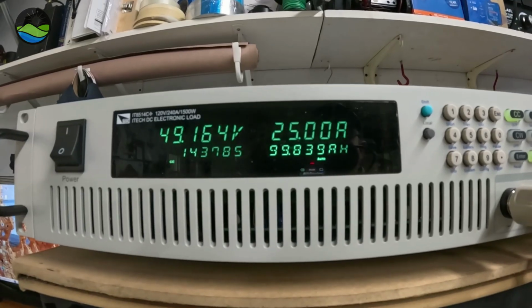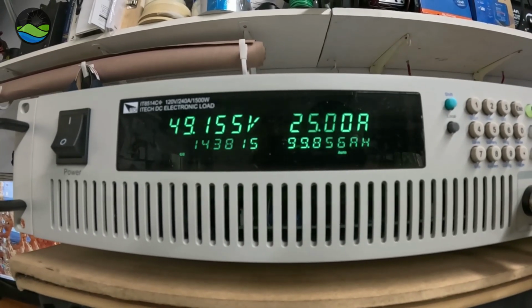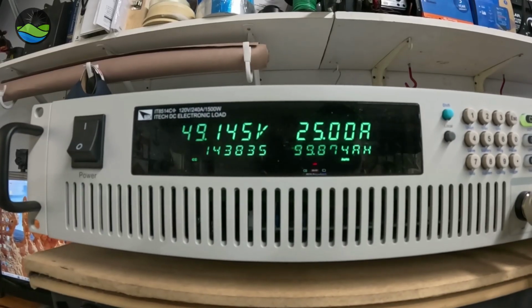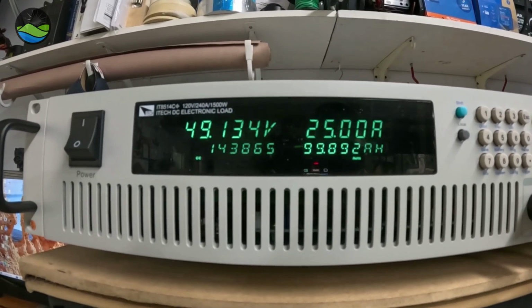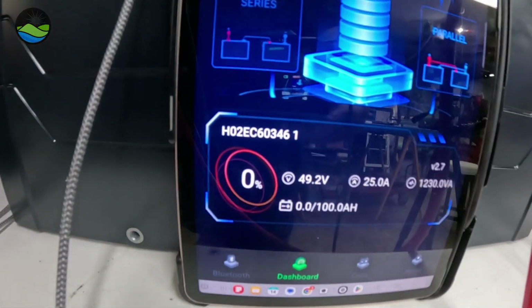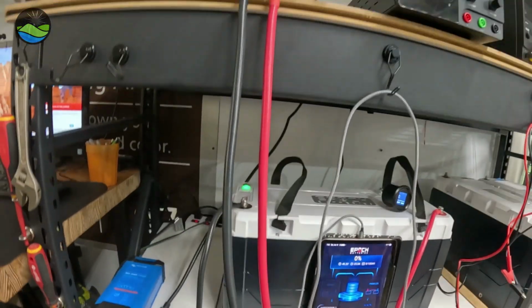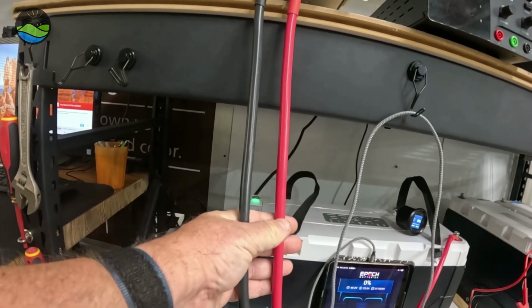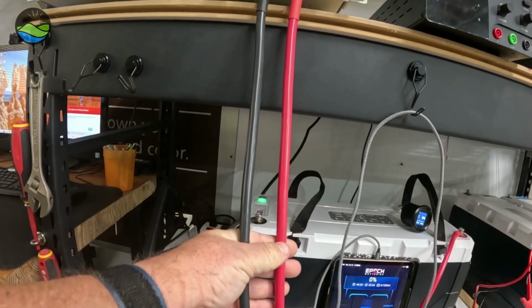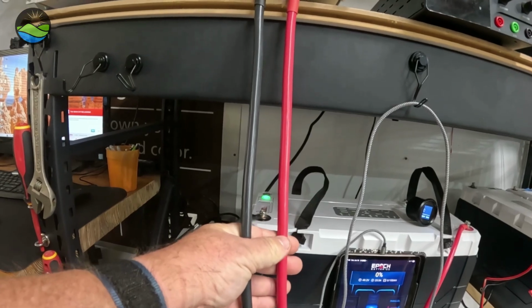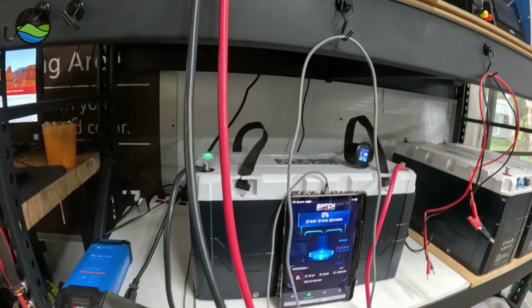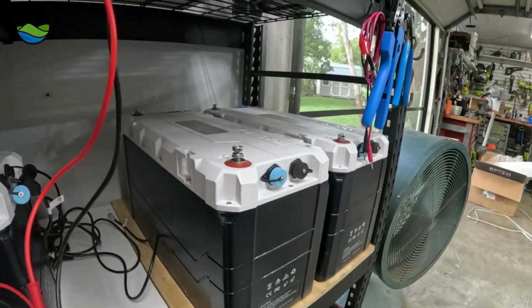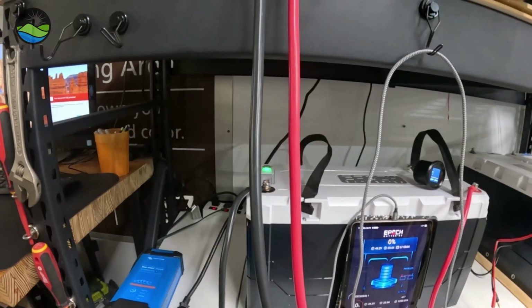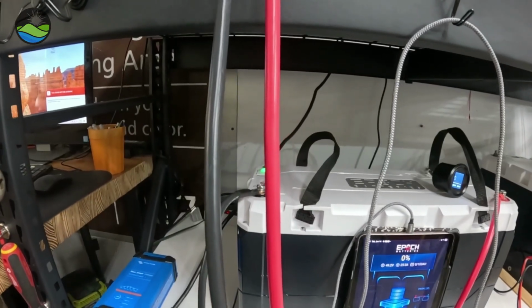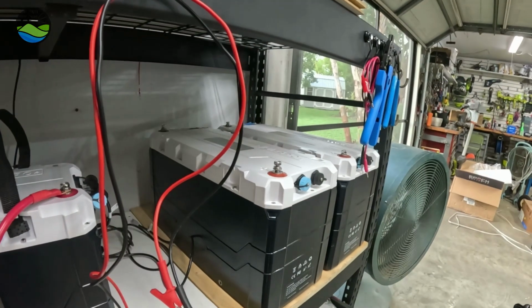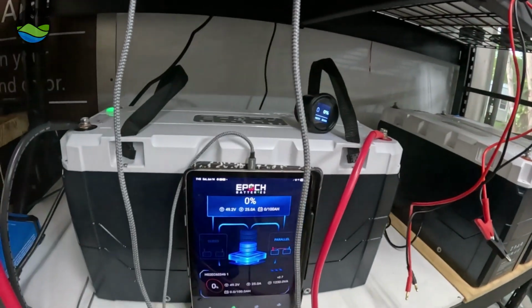One other thing to note, look at the voltage on the left side: 49.15, dropping now pretty good, 49.1, 49.2. The voltage drop under 25 amp load - these wires are only 2 gauge, I think, or 4 gauge, and they're ice cold. 48 volts is incredible compared to 12. There's a lot of energy in a 12 volt battery, but you're going to lose some of it to wires, even 4-aught wires, under the equivalent watts taken out of a 12 volt battery as compared to a 48.